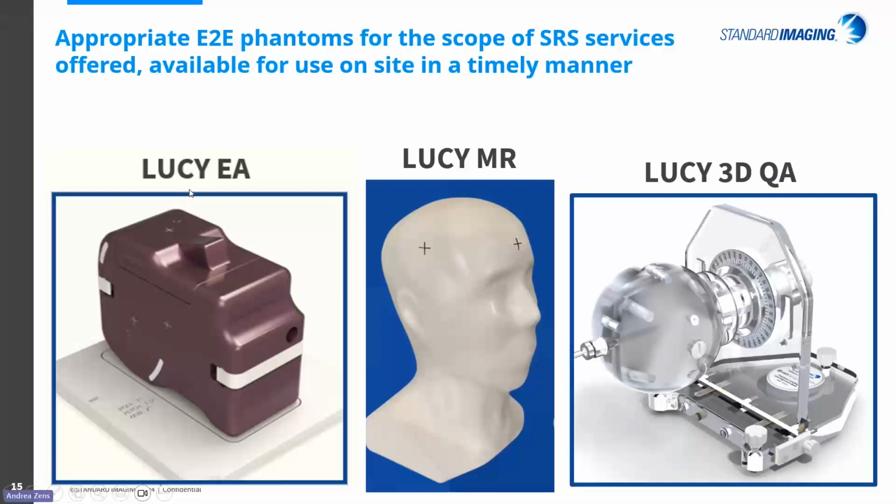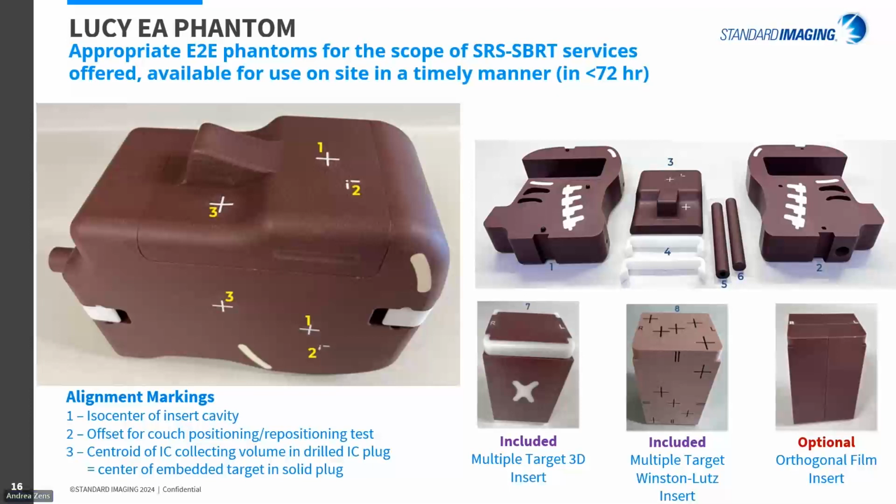So I'll go a little bit more in depth about our Lucy EA, since that is our most recent release that includes some key features that make it simple and quick to use. The Lucy EA Phantom is a pseudo-anthropomorphic phantom made of virtual water that is designed to perform comprehensive quality assurance tests for stereotactic radiosurgery SRS procedures.